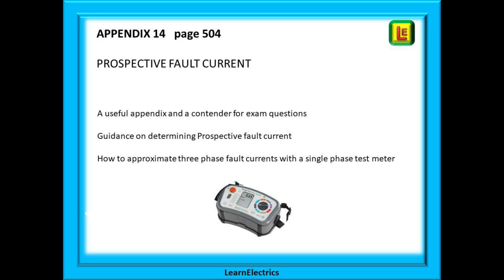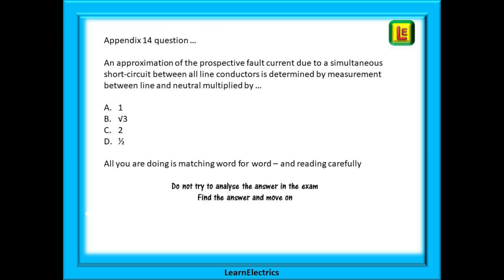Appendix 14 is about prospective fault current. How do we measure three-phase prospective fault current if our test meters can only test a single phase? The answers are here in appendix 14 — a popular appendix for exam questions. Do not try to remember all the information, just remember how to find it. A typical question might ask: an approximation of the prospective fault current due to a simultaneous short circuit between all line conductors is determined by a measurement between the line and neutral multiplied by — and all you are doing is matching word for word. If you've read carefully, the answer is two.